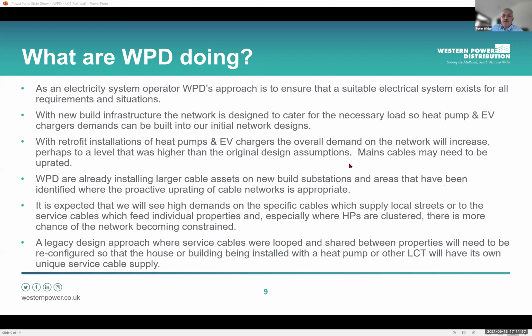Retrofitting of heat pumps and EVs is going to be one of the areas that needs quite a bit of forethought, because especially after the Second World War, rather small cable sizes were used as the service cable and the main cable. Another issue is that, especially from the 50s, 60s and 70s, they were looping services. If any LCT device is connected, the host DNO needs to de-loop that service, and that's done free of charge.